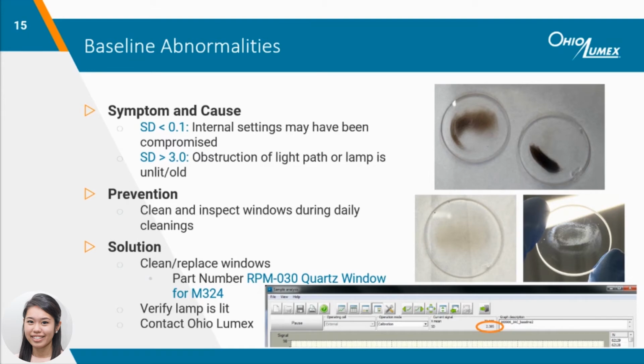If the SD is abnormally high, then the lamp may be unlit or getting old. If you cannot restart the lamp, please contact Ohio Lumex for service. An SD close to 0.1 shows the internal settings may have been compromised and will need to be sent into Ohio Lumex for evaluation.